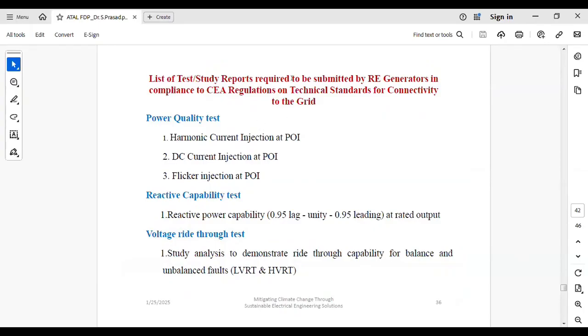A list of test or study reports is required to be submitted by RE generators whenever you are going to install the PV plant, before interconnection. All these reports have to be approved, in compliance with the CEA regulations on technical standards for connectivity to the grid. Power quality test, already discussed: harmonics current injection at PCC, DC current injection at PCC, flicker injection at PCC. These three reports we need to produce. Then a reactive power capability test, PQ capability test, VQ test, those things have to be submitted, verified and approved. Then voltage ride through, LVRT, HVRT, just now I have told you.